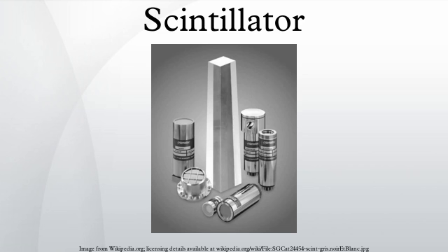High density reduces the material size of showers for high-energy gamma quanta and electrons. The range of Compton scattered photons for lower-energy gamma rays is also decreased via high-density materials. This results in high segmentation of the detector and leads to better spatial resolution. Usually high-density materials have heavy ions in the lattice, significantly increasing the photofraction. The increased photofraction is important for some applications such as positron emission tomography. High stopping power for the electromagnetic component of the ionizing radiation needs greater photofraction. This allows for a compact detector.